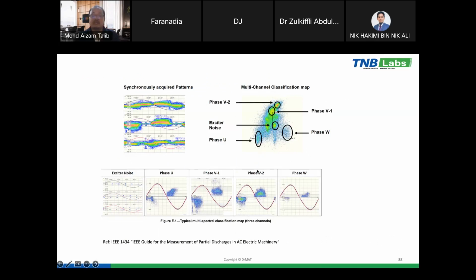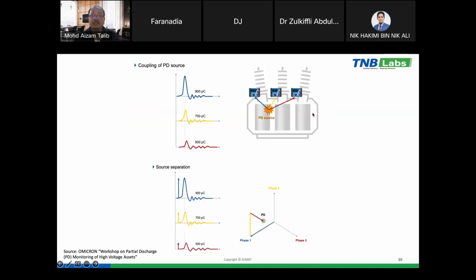Here is an example from the standards. For example, this is the transformer. Let's say the PD occurs at the blue phase. It means at the blue phase we will have a higher magnitude compared to the other phases. Because when we put a sensor on the phases, the PD signal will be picked up by the measuring instrument at the other phases, but with a different magnitude. So the PD detection at the blue phase will pick up a higher magnitude compared to the yellow and red.